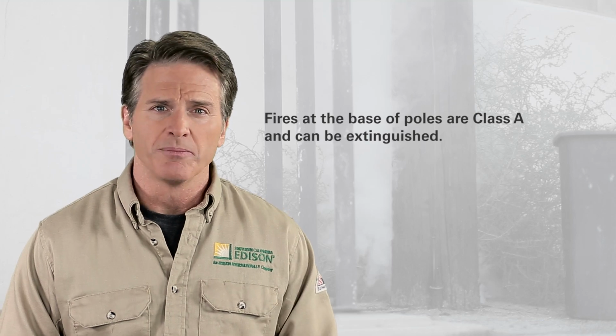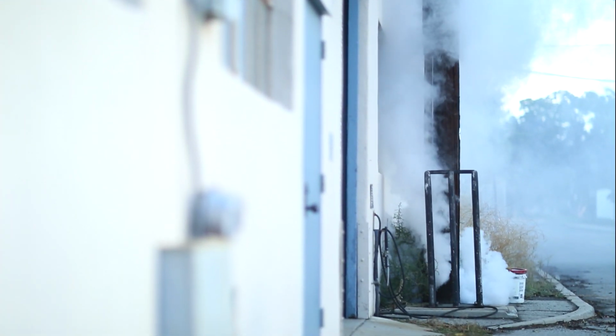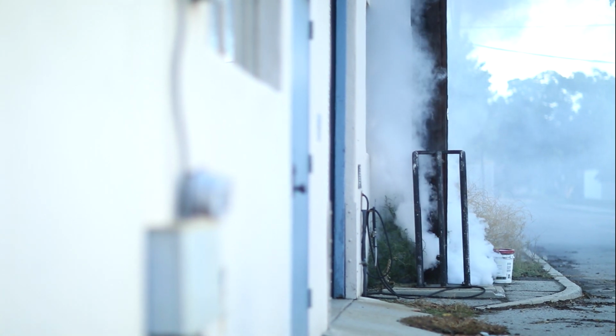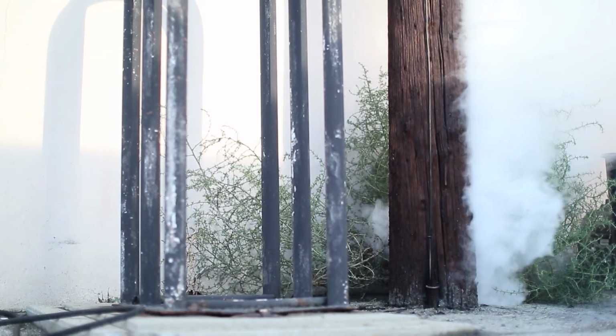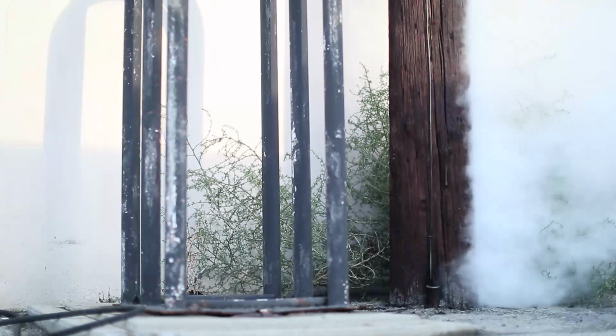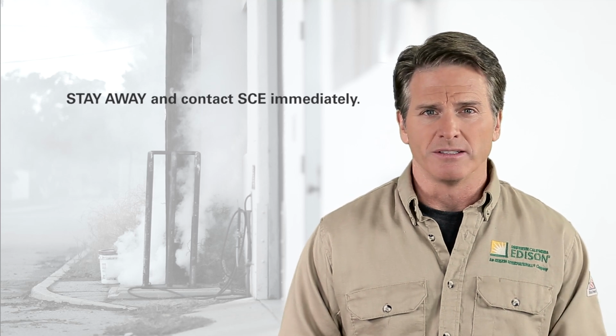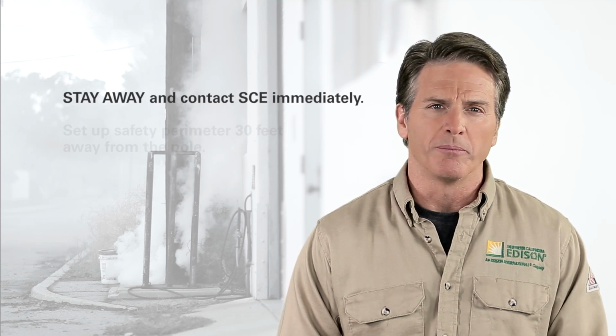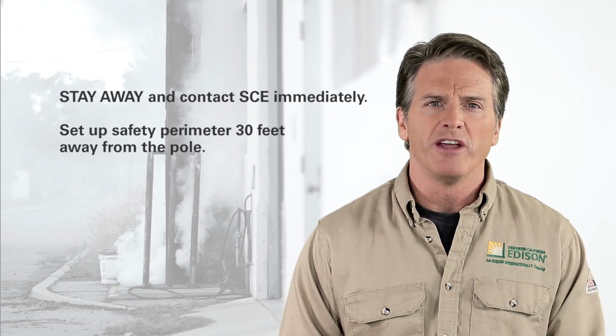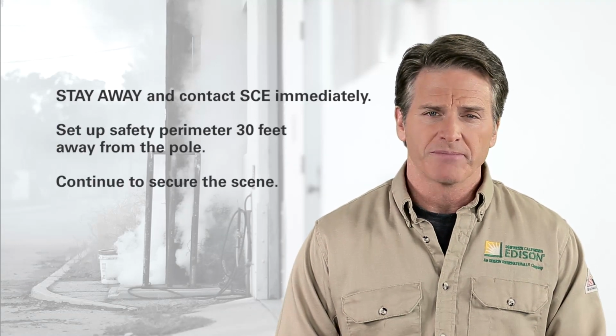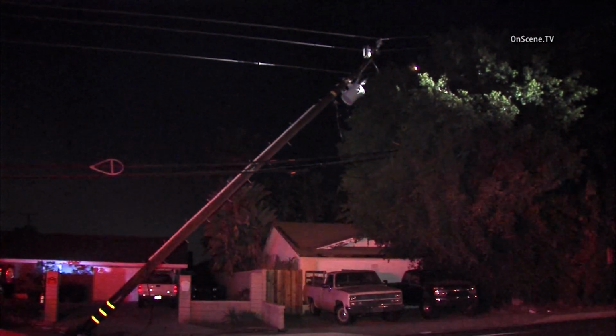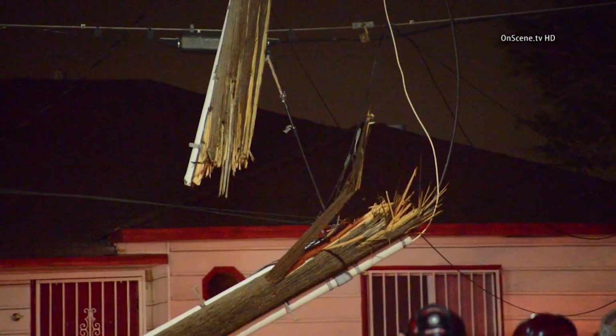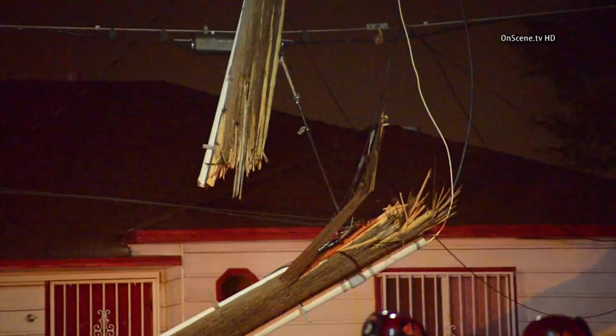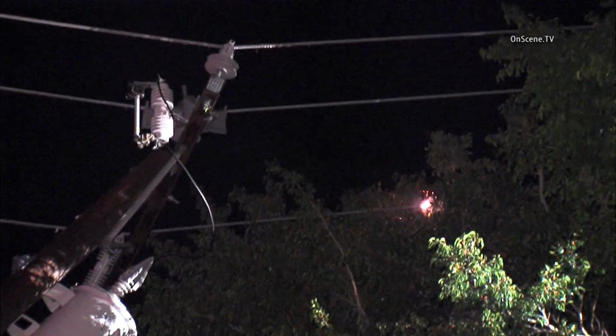Fires at the base of a pole are generally common Class A fires that should be extinguished. If it is evident that the fire at the base of a pole was caused by ground fire, you can put it out. However, if there are any doubts that ground fire is the cause, be aware that the problem could be caused by underground electrical conditions or a downed wire. When in doubt, stay away and contact us immediately to de-energize the location before doing anything more. Set up a safety perimeter at least 30 feet away from the pole and continue to secure the scene. In cases where fire has created the possibility of a pole falling on a structure, consult your departmental policy on how to act. If the policy is to extinguish the fire, use a fog pattern to suppress the fire.